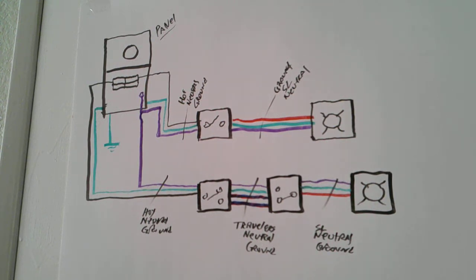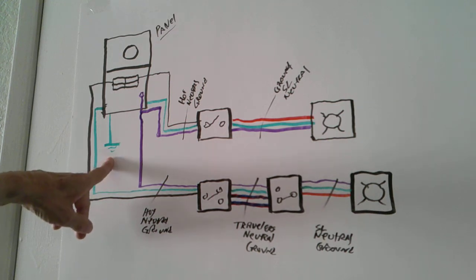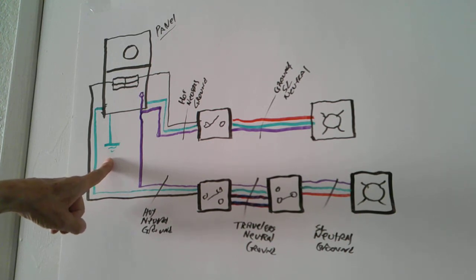So getting back to everything, our panel is always grounded, and we either ground that by code to a water line or a ground rod for residential. For commercial, we generally ground it to the building frame. We can ground it to a ground rod, or we can use a UFER ground or a plate ground.